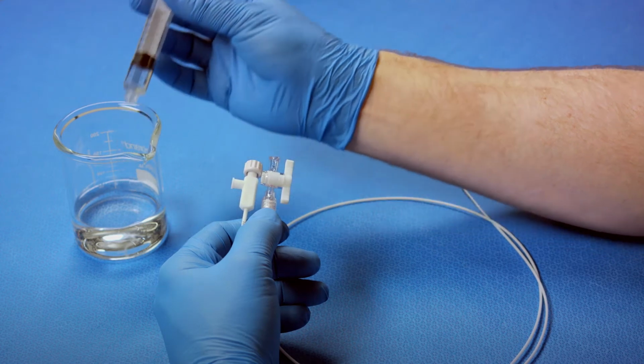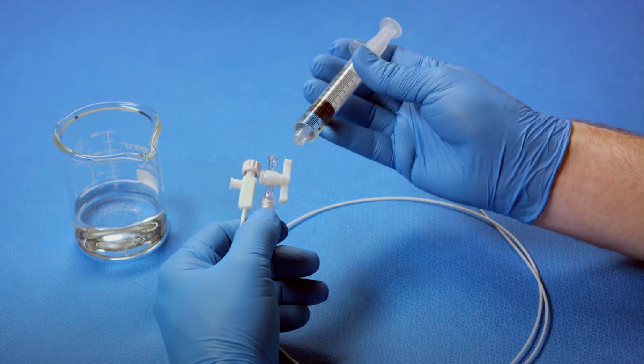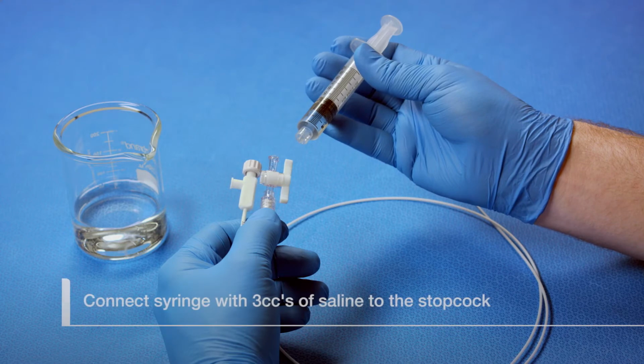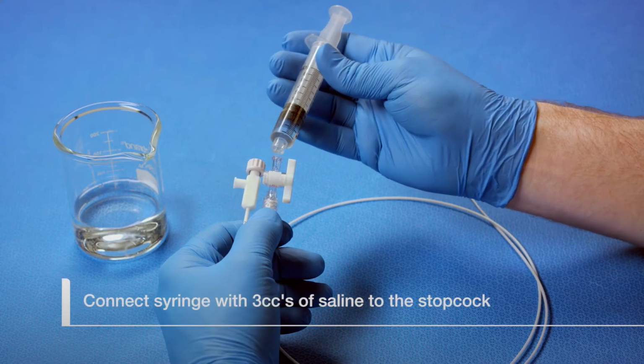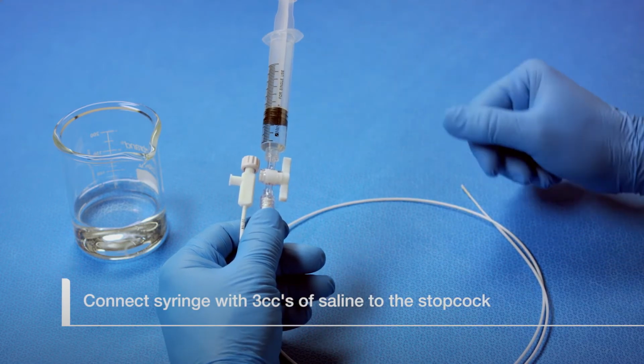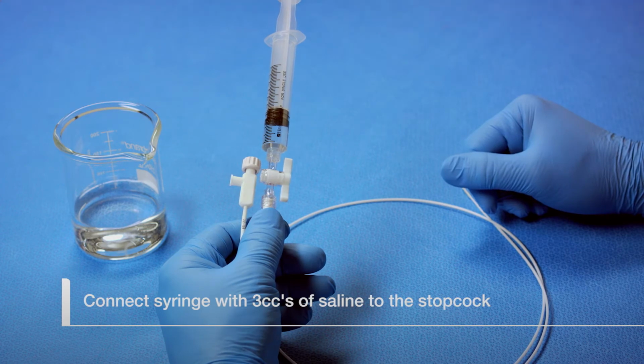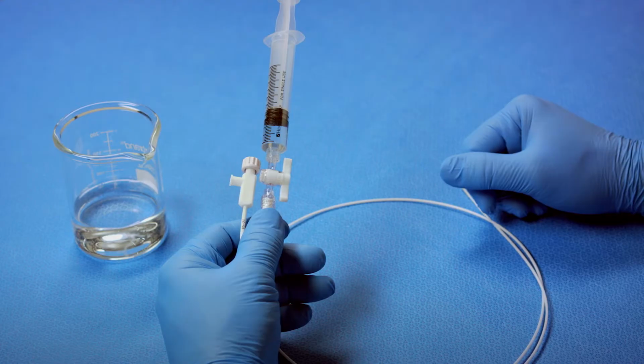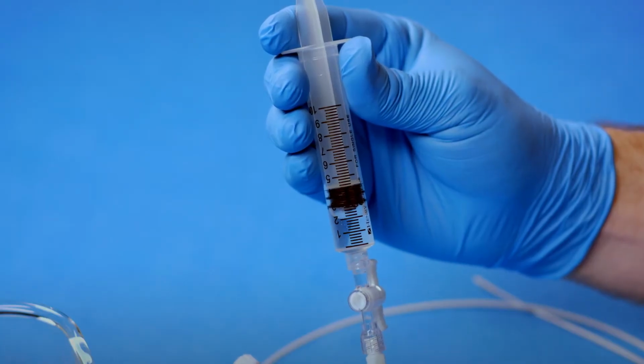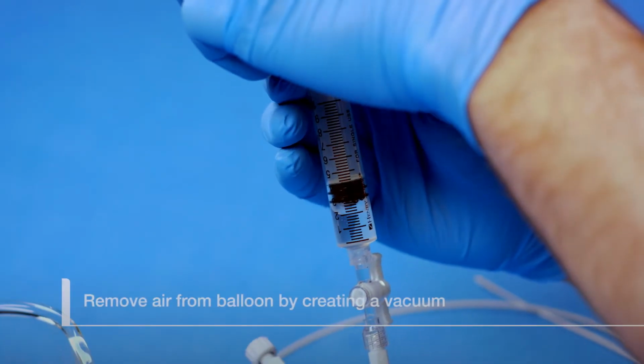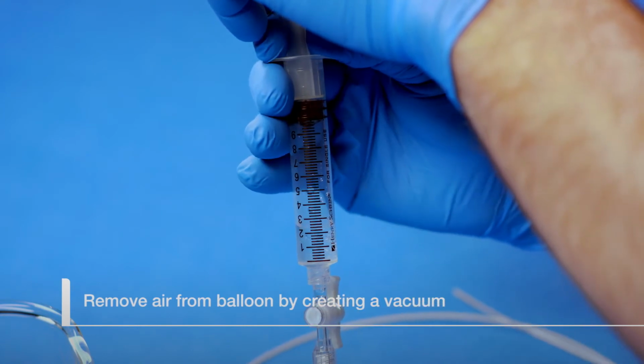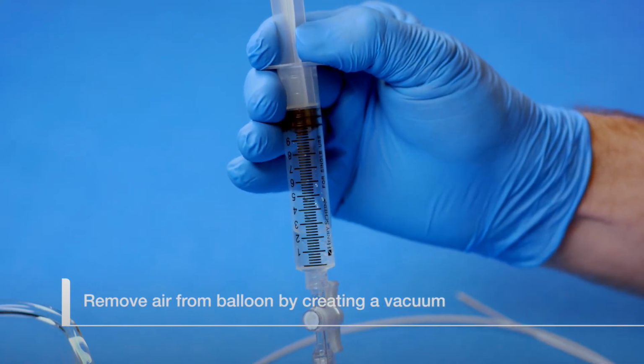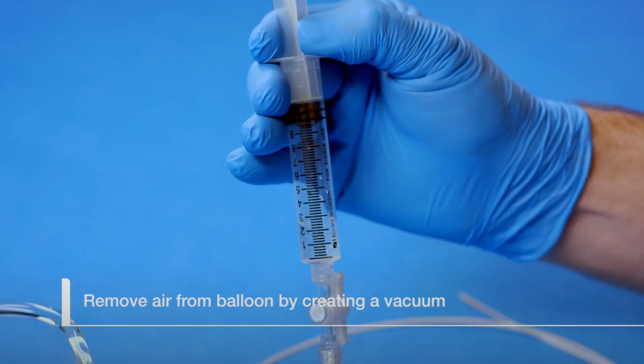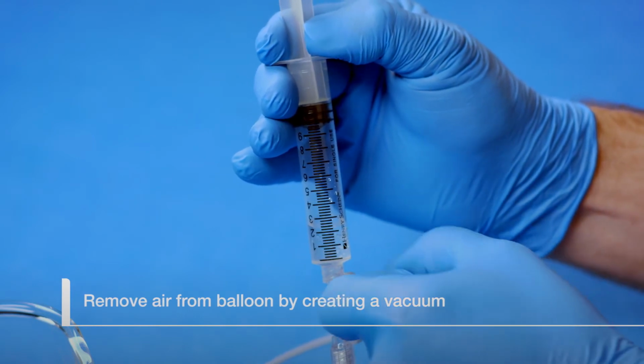Fill the 10 cc syringe with approximately 3 cc of sterile saline. Purge any air from the syringe and connect it to the stopcock port. Holding the syringe oriented with the plunger up, pull the syringe plunger to approximately the 10 cc mark and hold for at least 10 seconds to create a vacuum, removing the air from the balloon. While maintaining the vacuum, tap on the side of the syringe to assist in removing bubbles from the stopcock.